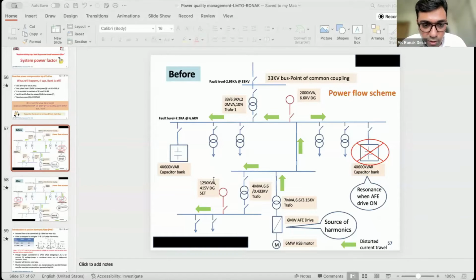The client, the customer, was not at all aware of what the symptoms were. In fact, this drive was installed 500 meters away from the main substation where these issues were happening. So was the problem related to the tuning of the drive? Normally an active front-end drive is meant for quality power, harmonics-free current and voltage, but here there was an issue. What could be the solution in that case? A filter or a choke at the input of the drive, or power factor compensation at the main substation, or removing the existing power factor compensation and replacing it with a passive harmonic filter.